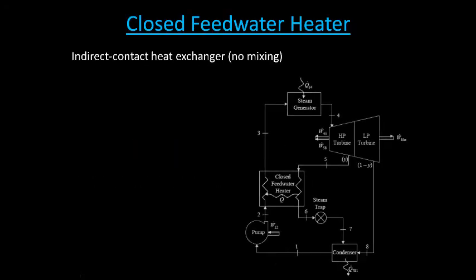A closed feed water heater is one where there's an indirect contact heat exchanger. So we're still exchanging heat, but we're not actually mixing the fluids together. If you see this in a diagram, we can see that we have one flow from 2 to 3 going by, another flow 5 to 6 going by, but they never actually touch.